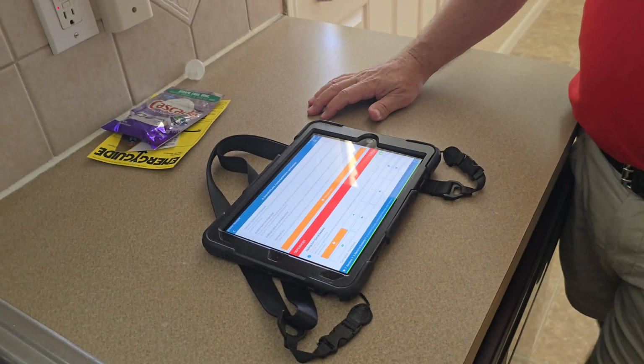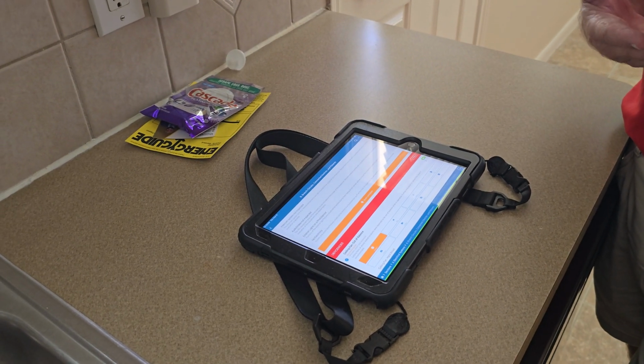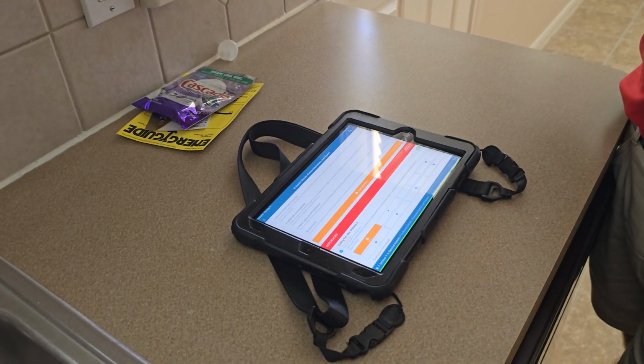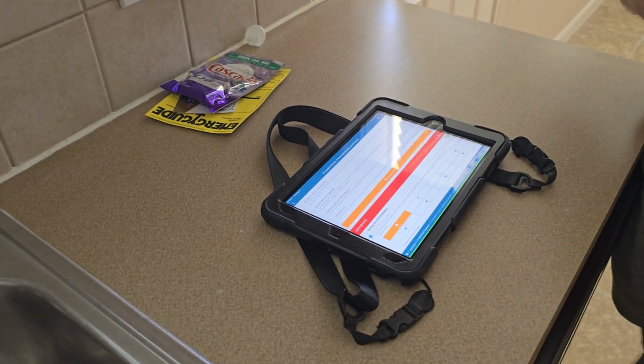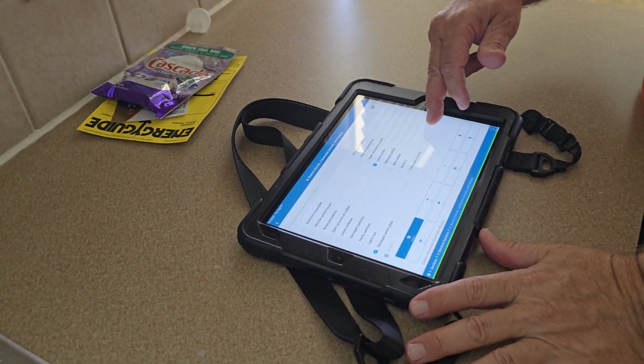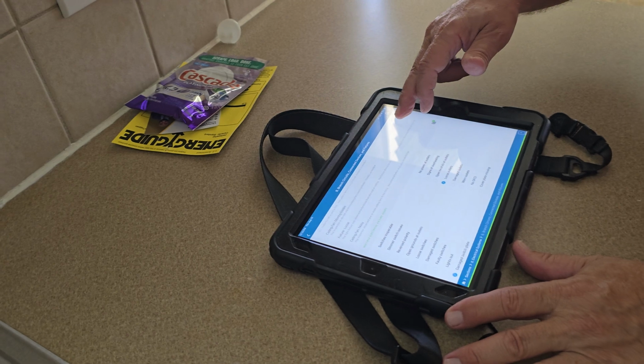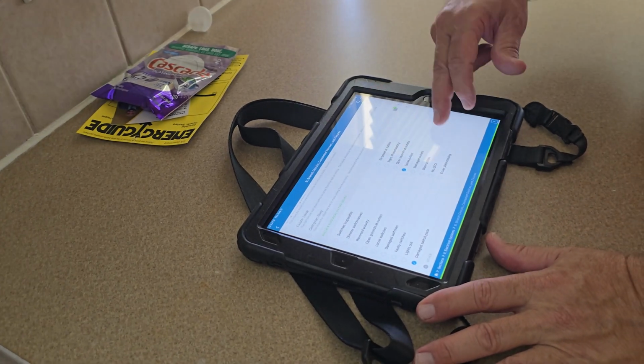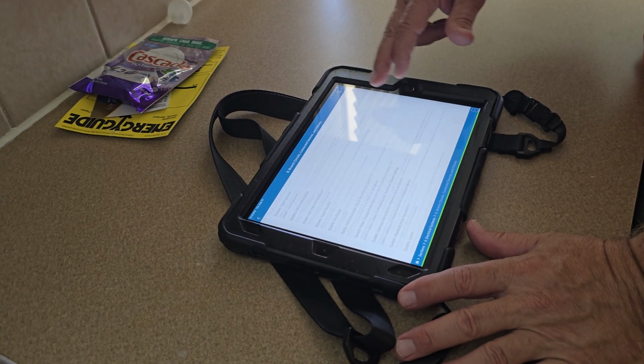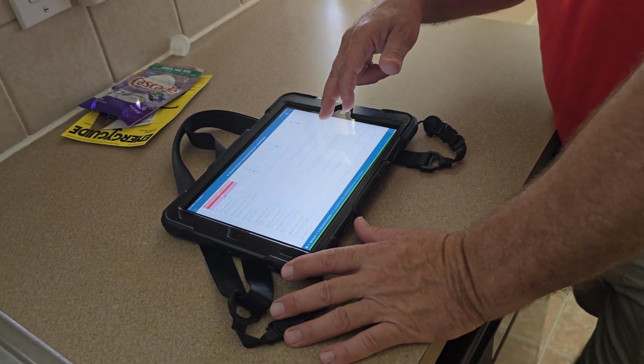One thing I look for is the GFCI protection in all the wet areas. So that's exterior, kitchen, bathroom, laundry room, garage. You got it in all those places, but not the laundry room. Hold on, let me make sure. Yep, just the laundry room. There's 2 outlets in there. And then a couple of loose outlets, a damaged switch plate, a couple of lights that don't work, probably the bulb.